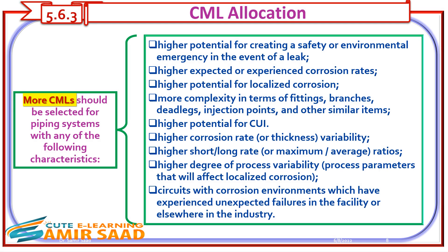More CMLs should be selected for piping systems with any of the following characteristics: higher potential for creating a safety or environmental emergency in the event of a leak; higher expected or experienced corrosion rates; higher potential for localized corrosion; more complexity in terms of fittings, branches, deadlegs, injection points, and other similar items; higher potential for CUI; higher corrosion rate or thickness variability; higher short-to-long rate or maximum-to-average ratios; higher degree of process variability; and process parameters that will affect localized corrosion.